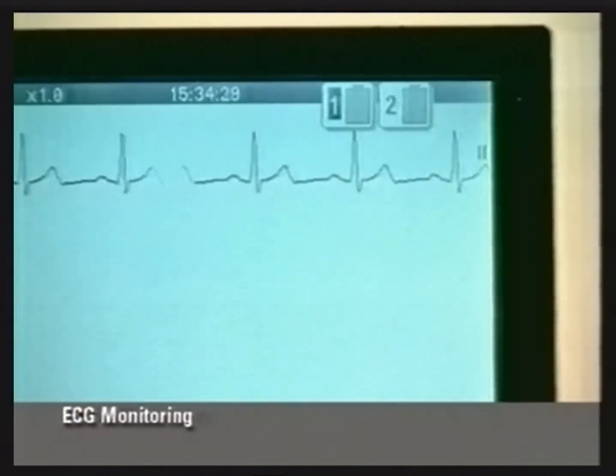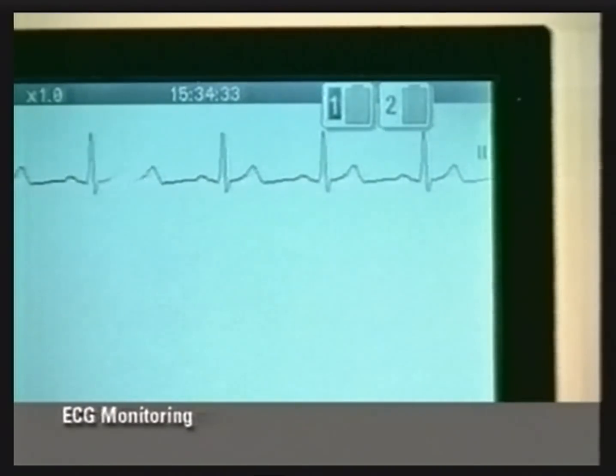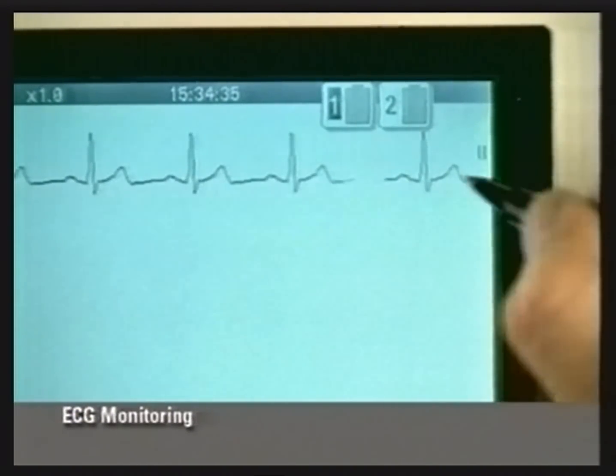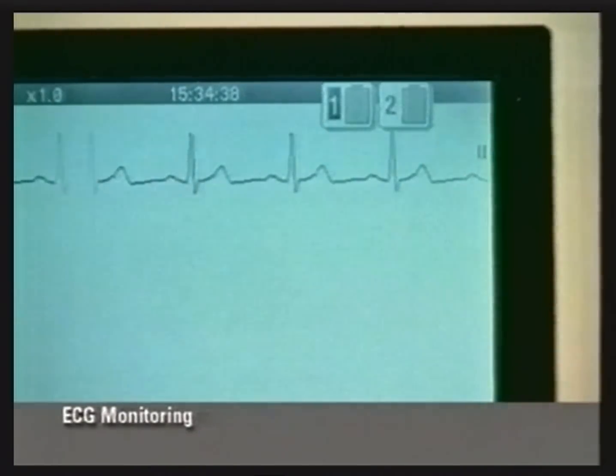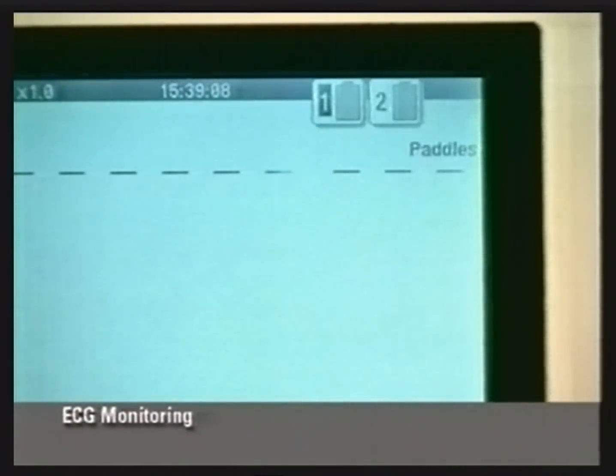Check that the ECG is displayed on the screen. If the power on default is lead 2, the patient's ECG and the indicator 2 are displayed. If the power on default for the ECG is paddles lead, the screen displays a dashed line and the lead indicated is paddles. To change to lead 2 or any other lead, press the lead button.